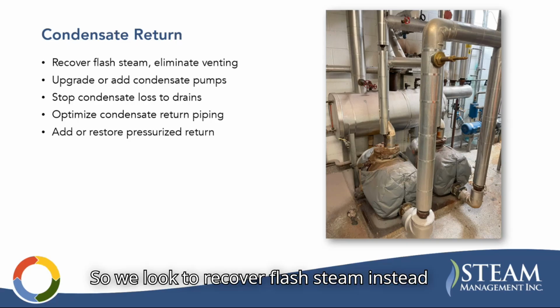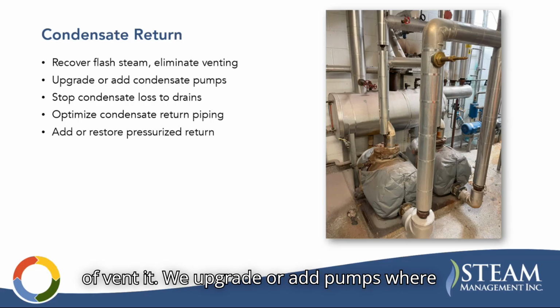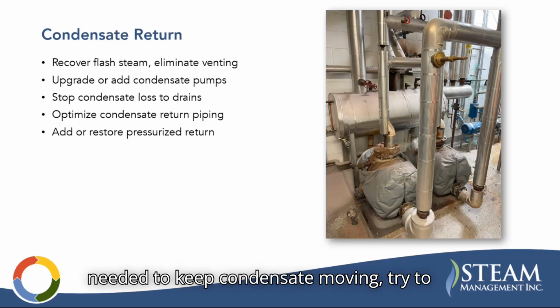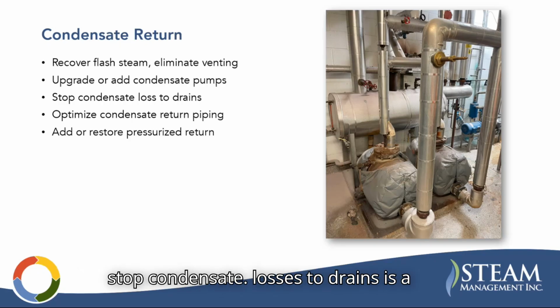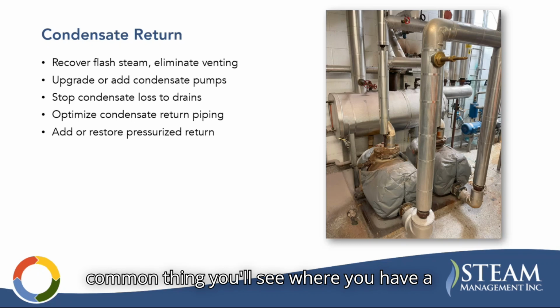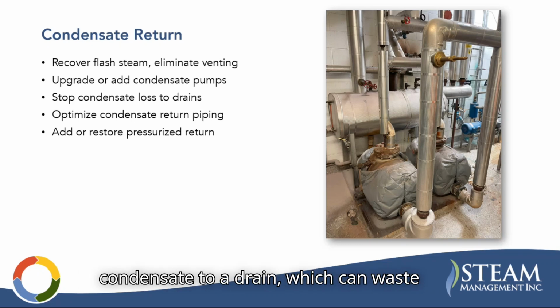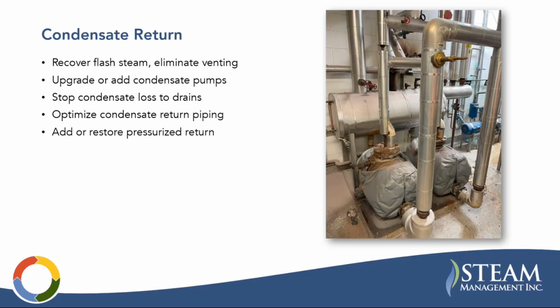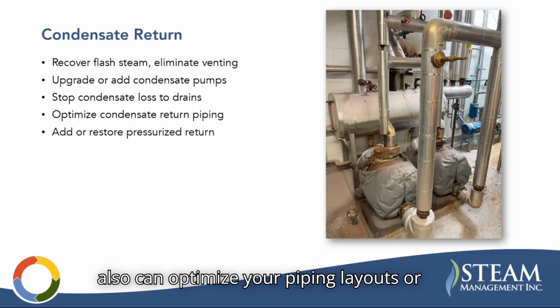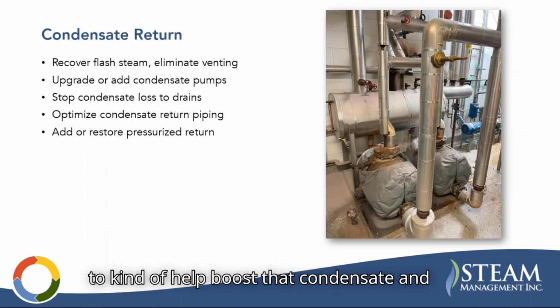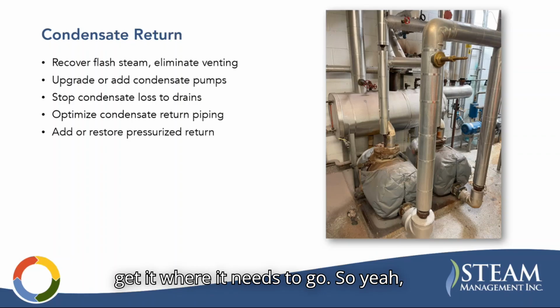So we look to recover flash steam instead of vent it. We upgrade or add pumps where needed to keep condensate moving. Try to stop condensate losses to drains. It is a common thing you'll see where you have a user using steam and they just dump the condensate to a drain, which can waste energy and water, but also can damage sewer systems. You can also optimize the piping layouts, add or restore pressurized return systems or pump traps to help boost that condensate and get it where it needs to go. So yeah, there's a lot of things you can do to improve condensate return.